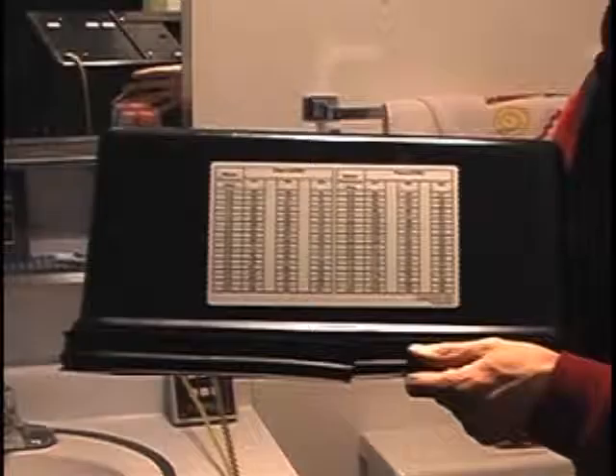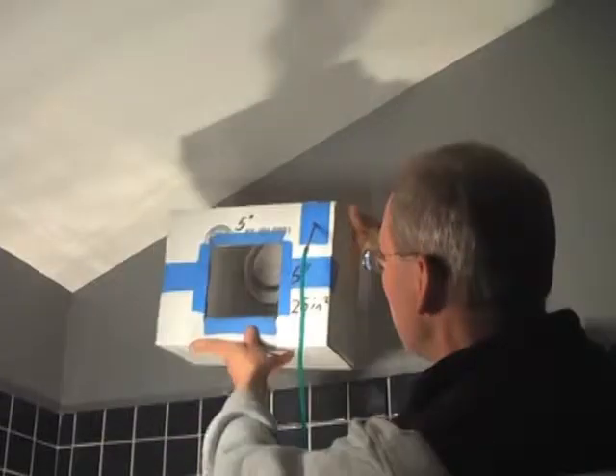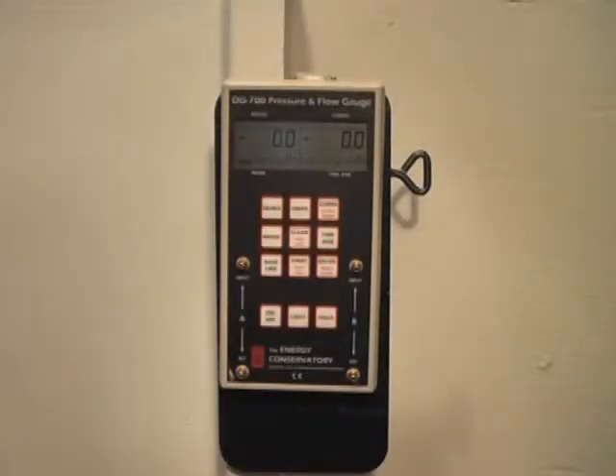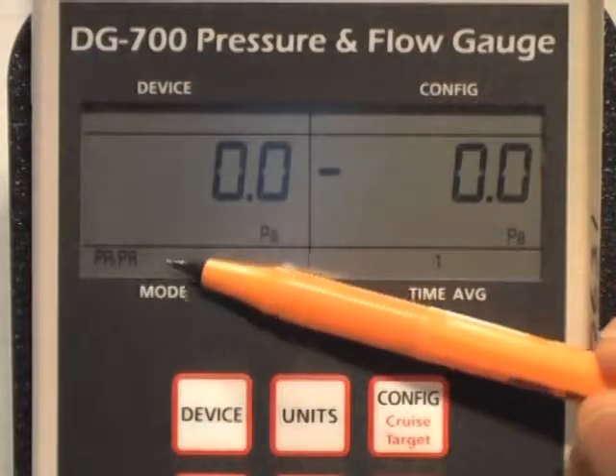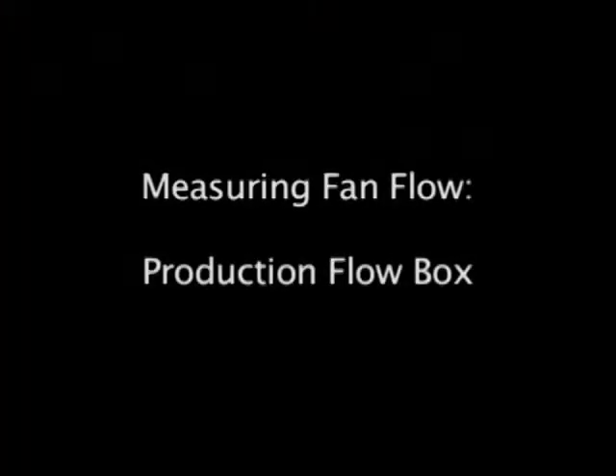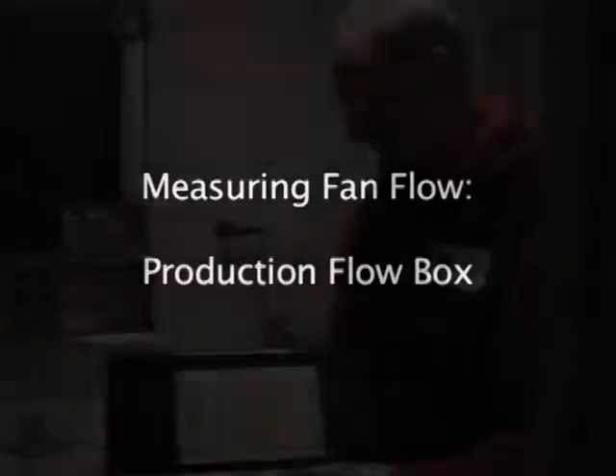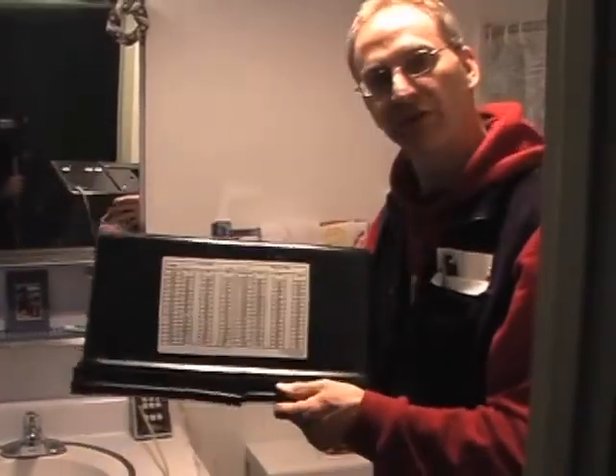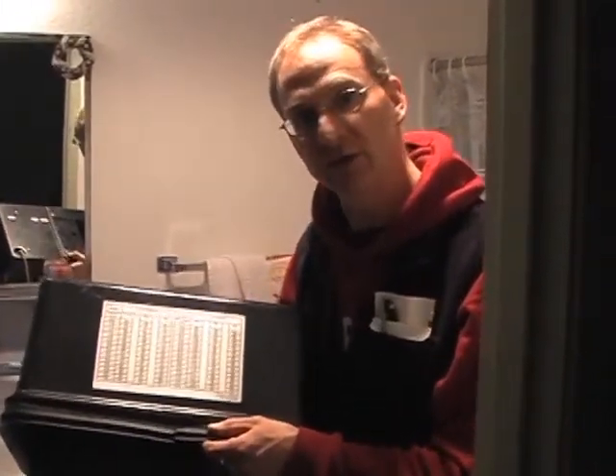You can estimate exhaust fan flow using a DG700 and a flow box. I will show you how to measure flows using both production and home-built flow boxes. To measure exhaust fan flow using the DG700, use the default mode setting of Pressure-Pressure. Here's our flow box, and what we can do is fit this over an exhaust fan like we would see in a bathroom.